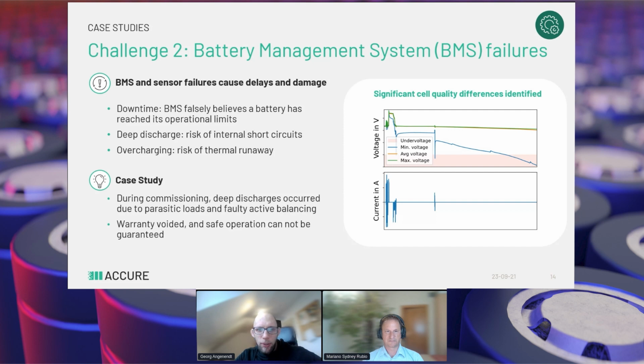The second challenge I want to present is battery management system failures. BMS failures can lead to downtimes, for example if the BMS falsely believes the battery system already reached its operational limits. It can also lead to deep discharge, which increases the risk of internal short circuits, or to overcharging, which increases the risk of thermal runaways.